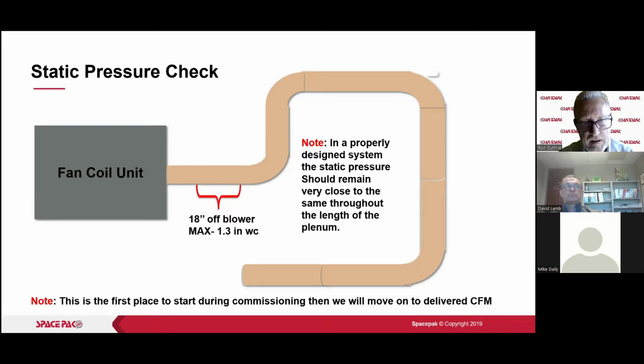But I would still go back in and actually check just to verify that it's showing the proper static pressure that we're seeing in the ductwork. Specifically, I would do it if we have an electric heater, if we have a heat pump, or if we just wanted electric heat. We do have electric resistance heat that we can add to these units. They're added on the outlet of the unit, and they do have an effect on the duct static pressure. So at some point, you may need to take a look at what you're seeing beyond that and compensate for that in your settings in the board. So keep that in mind.